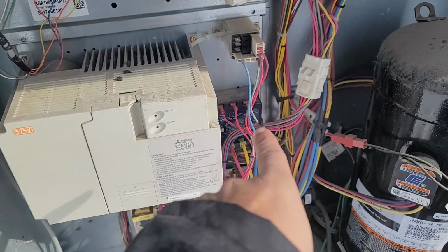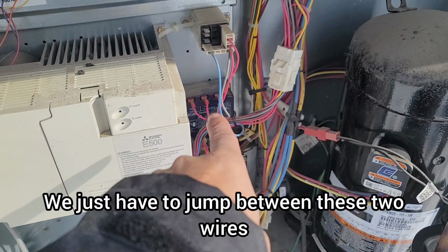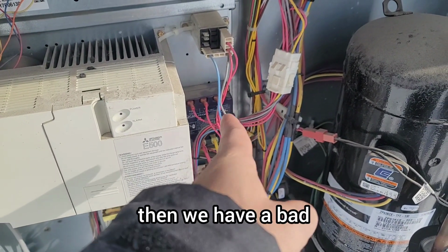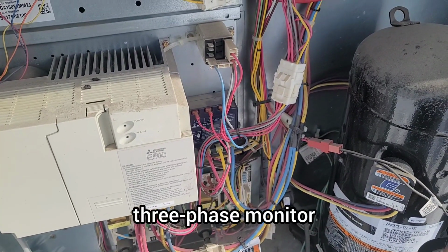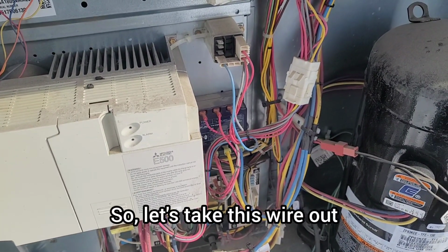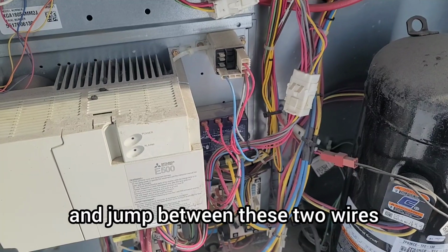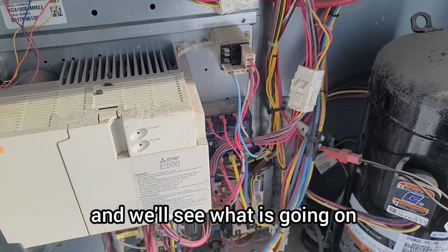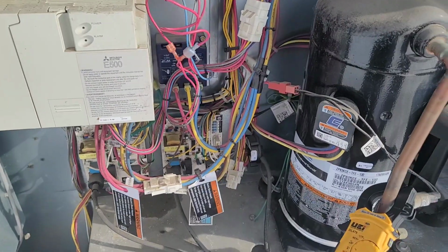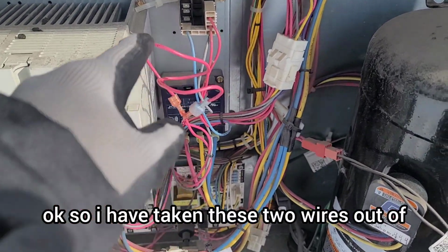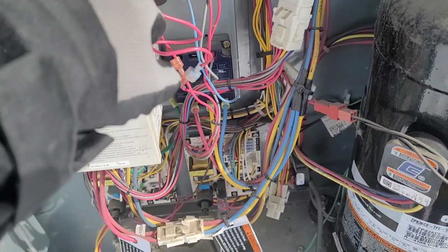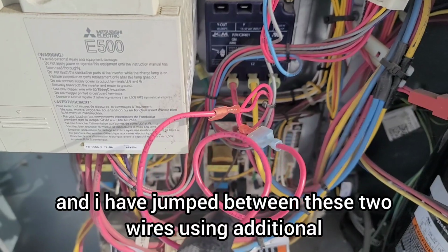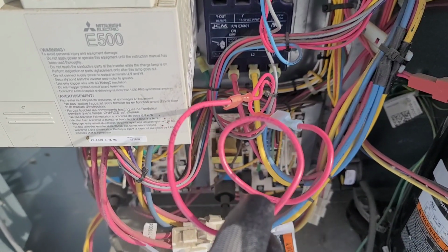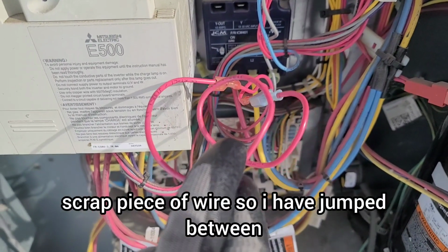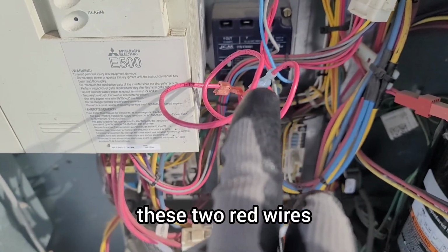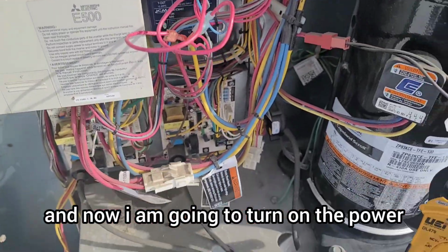So how can we test? We just have to jump between these two wires. If the unit runs, then we have a bad three-phase monitor. So let's take this wire out and jump between these two wires, and we'll see what is going on. Okay, so I have taken these two wires out. Of course the power is off, and I have jumped between these two wires using an additional scrap piece of wire.